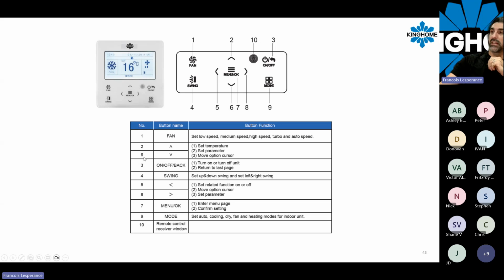This thermostat here, so our wire controller XK76, has the same ability as the remote controller. You can control the unit, setting the fans, setting the temperature, on off, the louver. You can adjust the louver directly on this wire controller, and you still have a small window here. The round window is an infrared receiver for the remote controller. So for example, if you have a cassette unit and it's up at the ceiling, but the ceiling is very high, and you have this wire controller on the wall, you still can use your remote control pointing at this infrared here and change the temperature with your remote control.